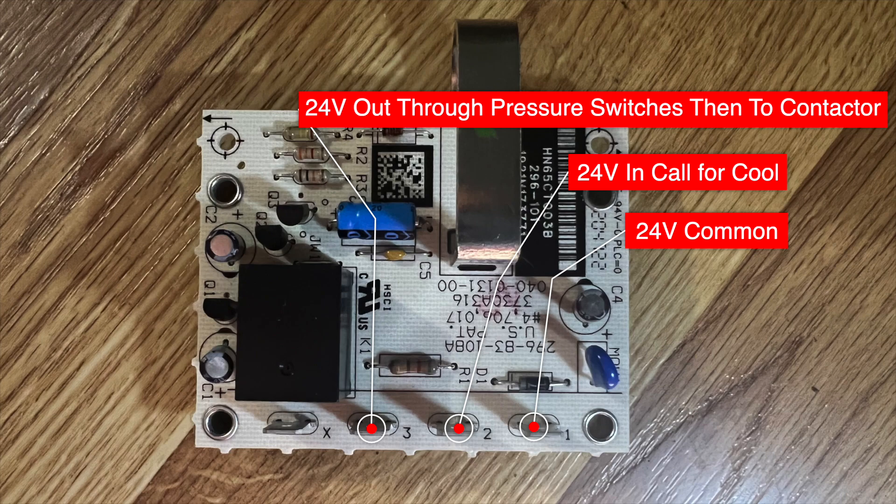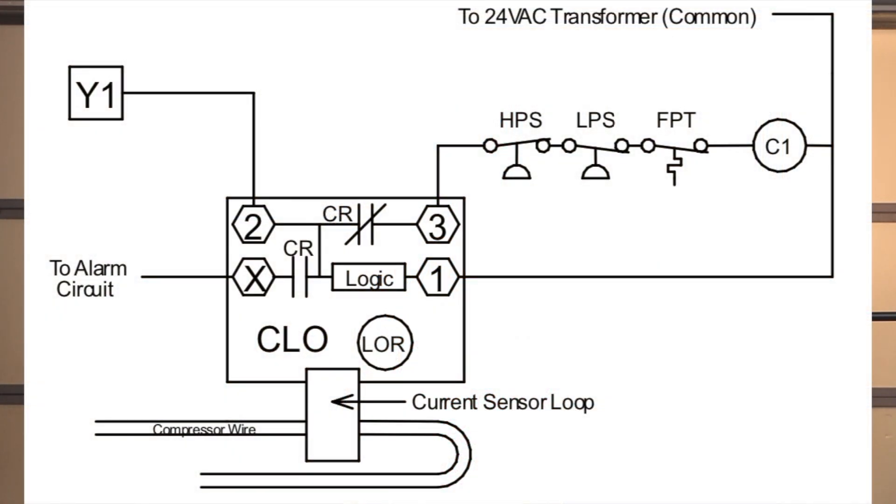Terminal three is going to output 24 volts — basically Y — and it's going to go through the high pressure switch, the low pressure switch, and then into the contactor. The other side of the contactor connects back to common, which also connects to terminal one. Now, X — we'll explain that. What happens is you receive 24 volts from Y via the thermostat into terminal two. The logic circuit sees a call for cooling and sends 24 volts out of three, through the high pressure switch, through the low pressure switch, hitting the contactor.